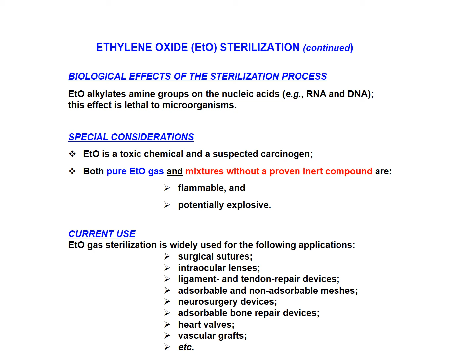The ethylene oxide sterilization method has several advantages. First and foremost, it has high penetration ability. This capability assures that all facets of the three-dimensional structure of the various implantable devices are sterilized. It is a very effective method, even at low temperatures. Remember, it works at temperatures between 30 and 50 degrees centigrade. It is compatible with many types of materials, including polymers, which are very sensitive to temperature ranges because they melt at high temperatures.